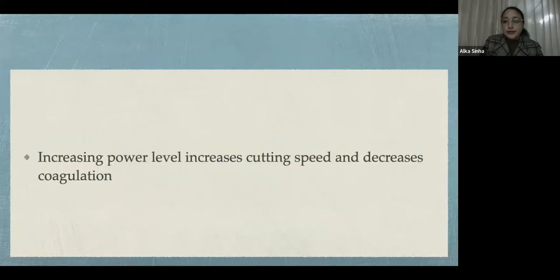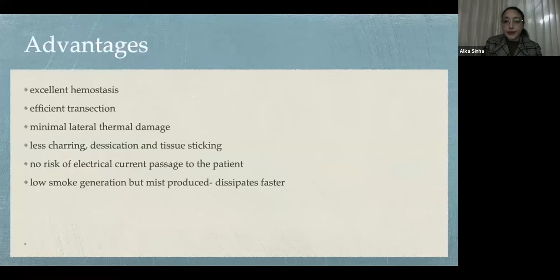Most of these devices have different power levels, which we can adjust to achieve a balance between coagulation and cutting. For example, in the harmonic, as we increase the power setting, there's increased cutting speed and less coagulation. This can be adjusted according to the surgery we are doing.